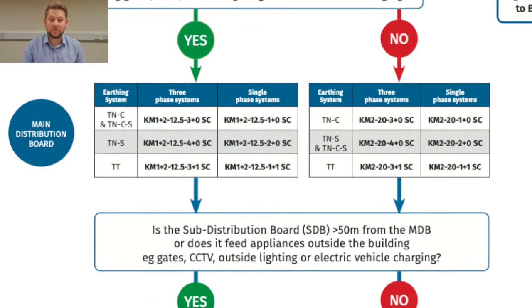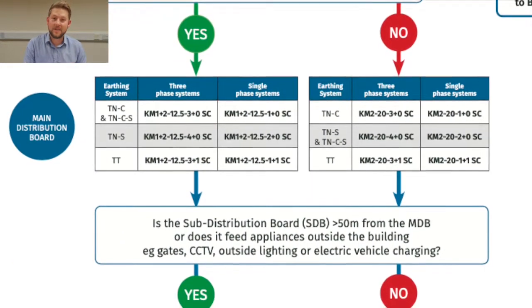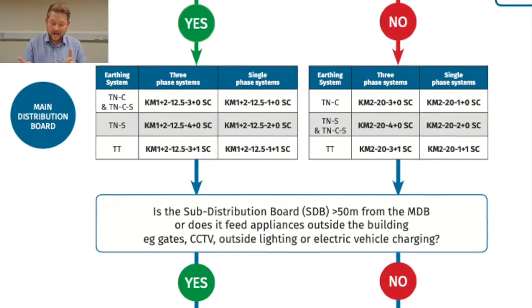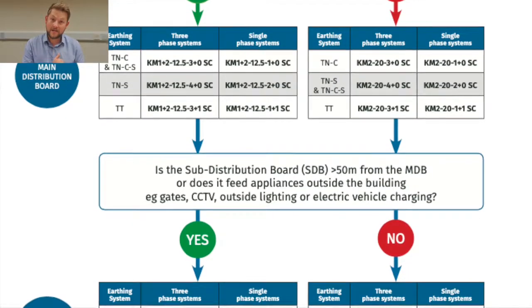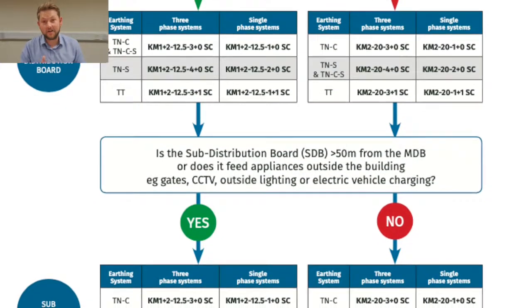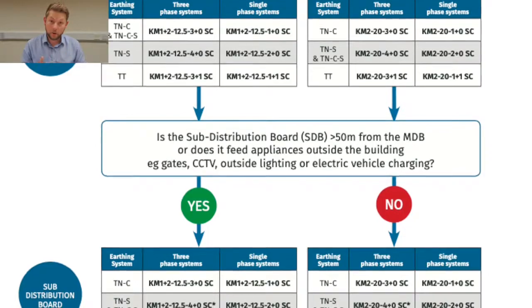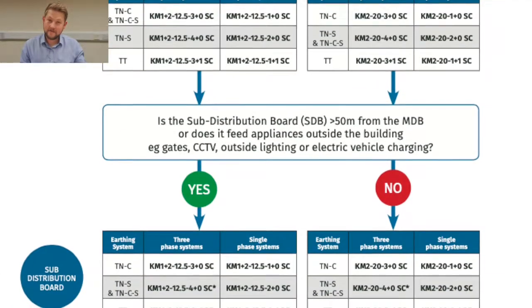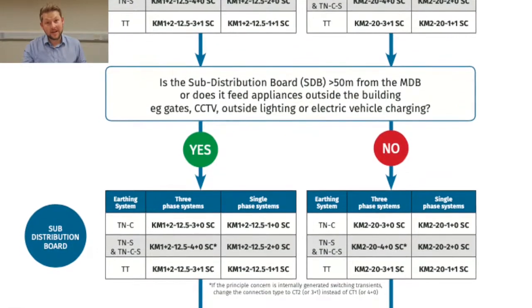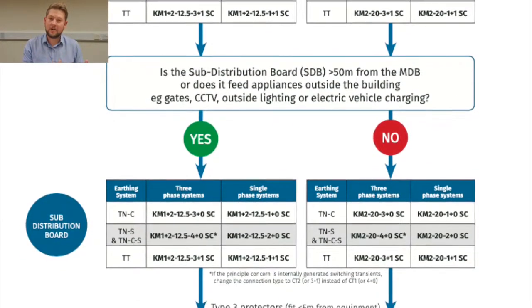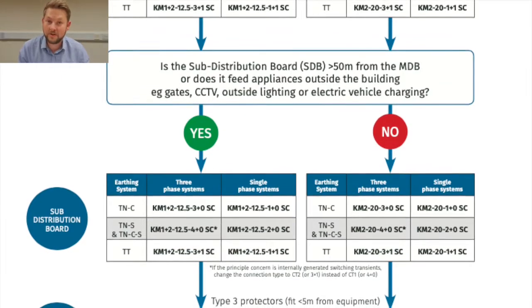Once we've got the correct main distribution board device selected, we can move on to sub distribution boards. Again, just a couple of questions: is the sub distribution board more than 50 meters from the main distribution board, and does it feed outside of the building? If it does, or if it is further than 50 meters, then again a type 1 and 2 device. If it's over 10 meters but doesn't feed outside of the building, then we're looking at a type 2 device.